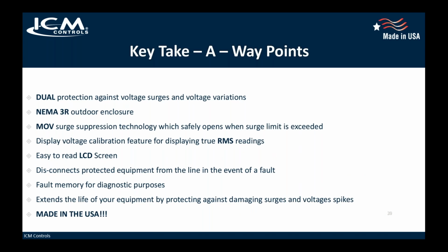All right, so some key takeaway points on the 493. Dual protection against voltage surges and voltage variations, okay? So you got not only line voltage monitoring, but surge suppression in one box. You got a good NEMA 3R rated outdoor enclosure. You got thermal MOV, TMOV surge suppression technology, which safely will fail once the maximum limit of 100,000 amps and 1,020 joules is met. You got a display voltage calibration feature, which allows you to tune your display voltage to true RMS readings, which gives you more pinpoint accuracy.